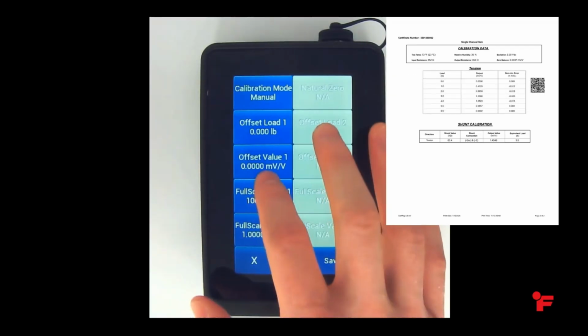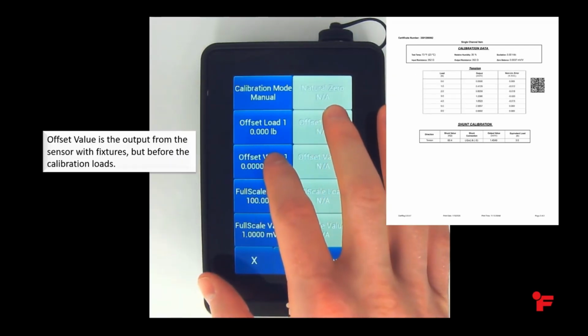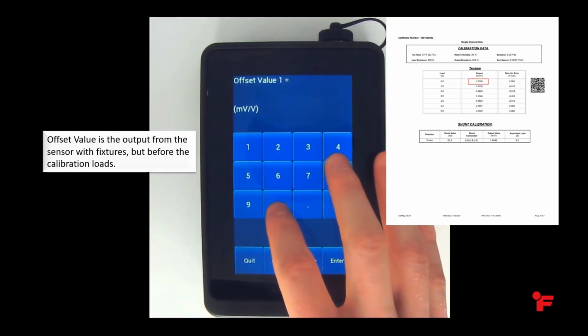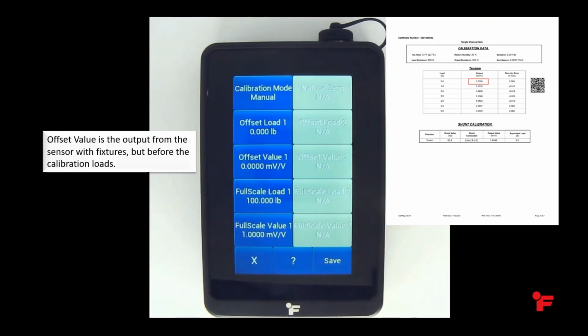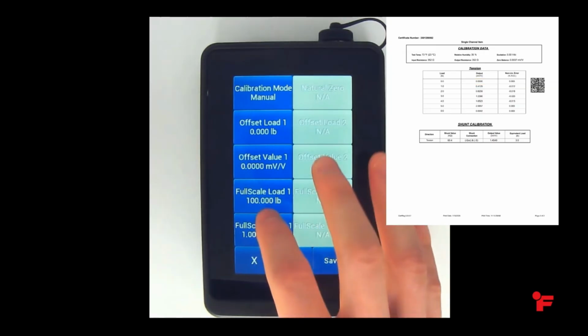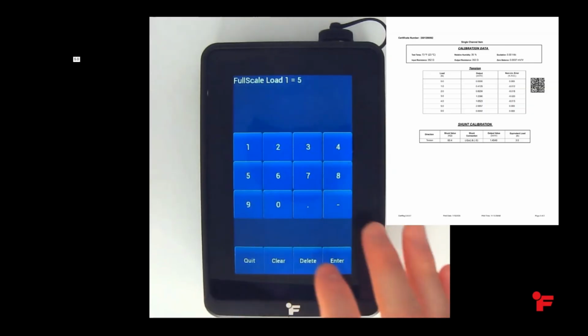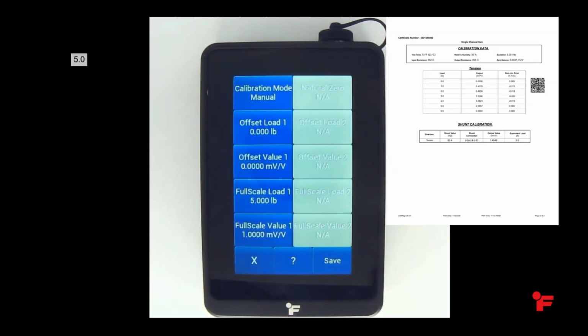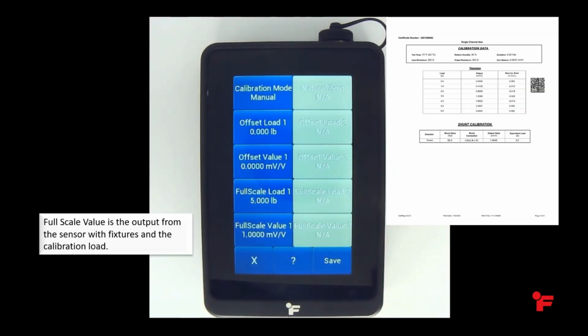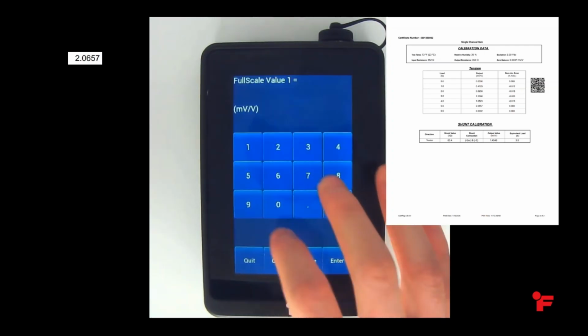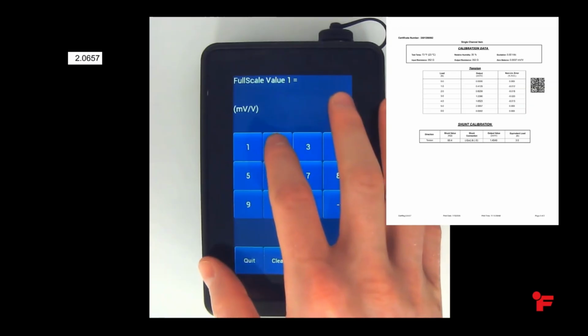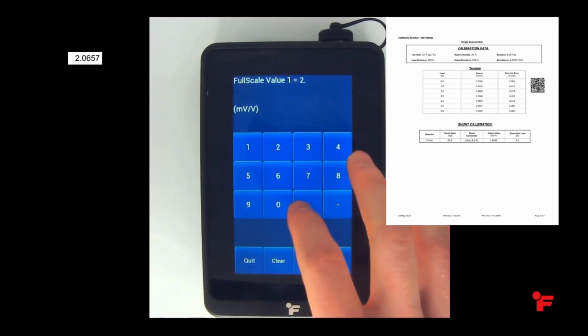The first row in the calibration table shows as 0 load and 0 millivolts per volt. So we will set offset load to 0 and offset value 1 to 0 millivolts per volt. Full scale load 1 is the capacity, which is 545 pounds. The calibration certificate table shows that the last loading point of 545 pounds generated 2.0657 millivolts per volt. We will set full scale value 1 as 2.0657.